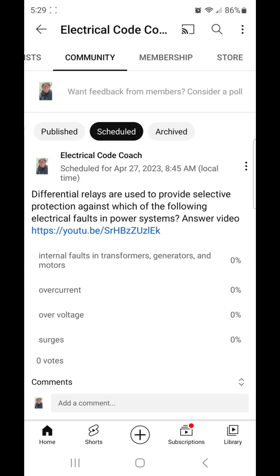Let's say we have phase A and phase B. The current is going good, everything is fine, and then all of a sudden there is more current on phase A because of a fault — a motor winding issue or different things that could potentially be the problem. There is going to be an inrush of current on phase A, it is going to read that discrepancy in current, and it is going to open the relay.